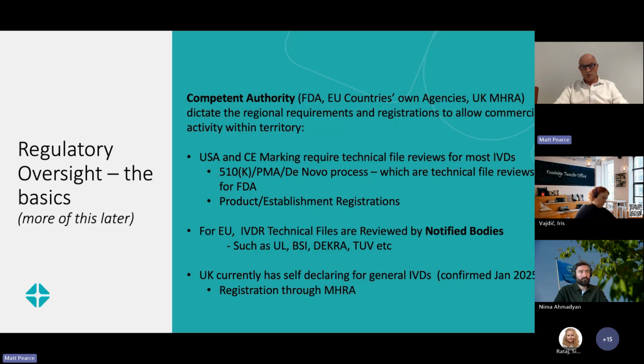In the US, that's what they call a 510K, where you're actually submitting the technical documentation to show that your product is substantially equivalent to an existing competitor or an existing product. Or if there is no existing product, then it's a de novo process. But if it's a high risk item, then it's called a PMA, a pre-market approval. And so those are the three methods of going in through to the FDA. De novo and PMA are very similar in terms of process, with very high levels of scrutiny from the FDA. With the 510K, you are really setting your technical file up to compare it against another alternative system.